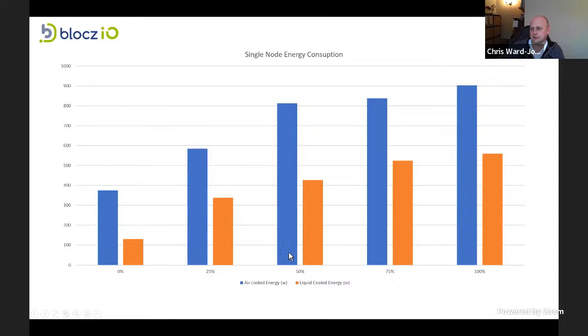If you look at the 50% utilization mark, average server utilization is probably around 50%, and you're looking at about 46%, just over 46% saving in energy. If you're running a data center that consumes 5 megawatts, you're now consuming 2.5 megawatts. The carbon impact of having to produce half the amount of electricity is truly staggering when you think about it. This percentage difference is near enough maintained throughout. In fact, when we averaged everything out, we were just shy of 50% energy saving, averaging out all the different workloads that we tested.